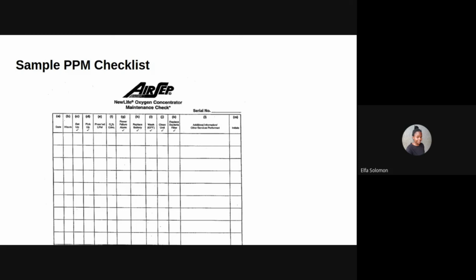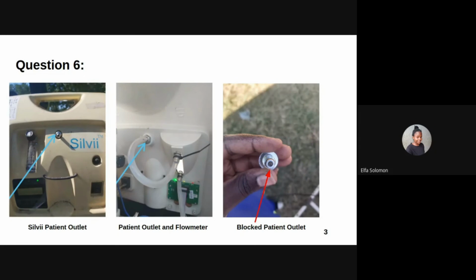So when the oxygen concentrator is switched on and everything is connected, you would expect air to be coming out of the patient outlet. So if there is no air coming out, the problem could be some sort of blockage in the system. I would advise you to do a blockage test by removing one pipe at a time, starting from the sieve bed outlet down to the patient outlet. In addition to that, you should also check the patient outlet fitting. I have noticed that sometimes insects enter through the patient outlet fitting and build a nest, which leads to blockages. This mostly happens when the concentrators stay for a long time without use.